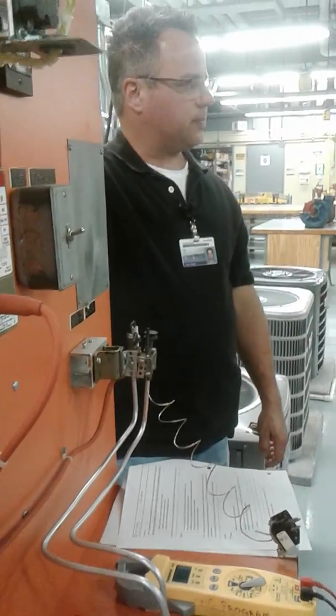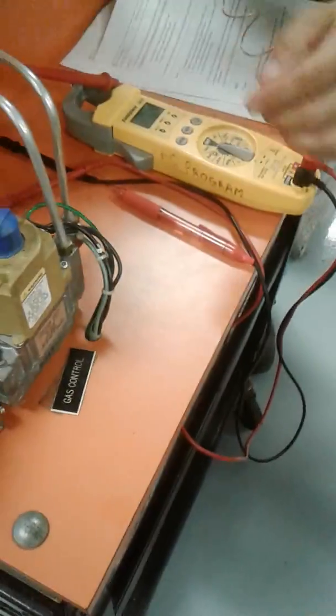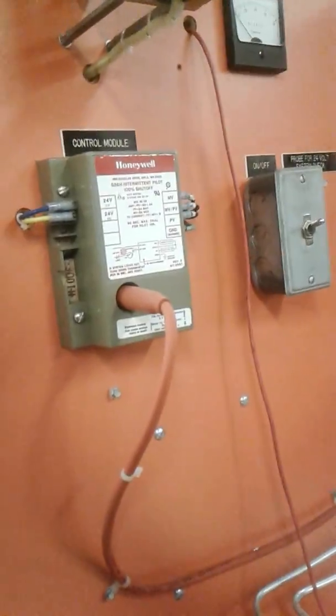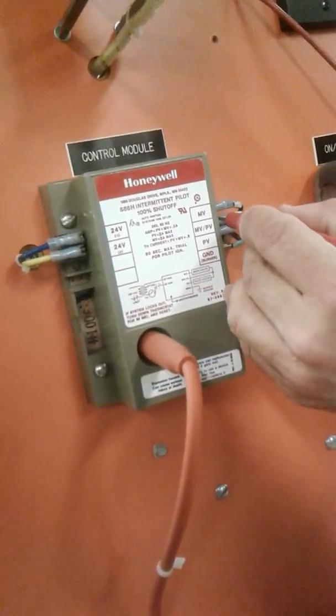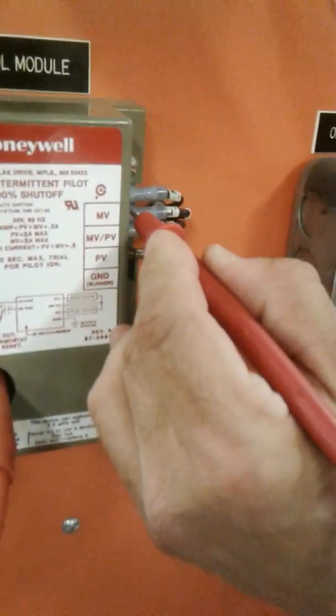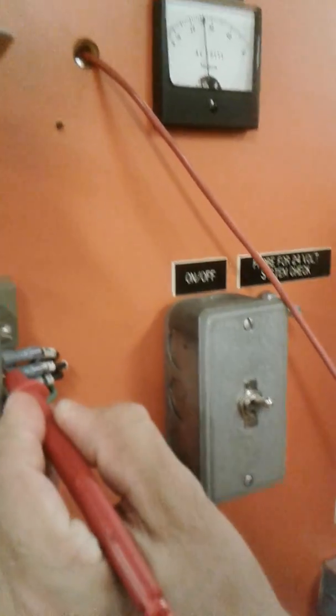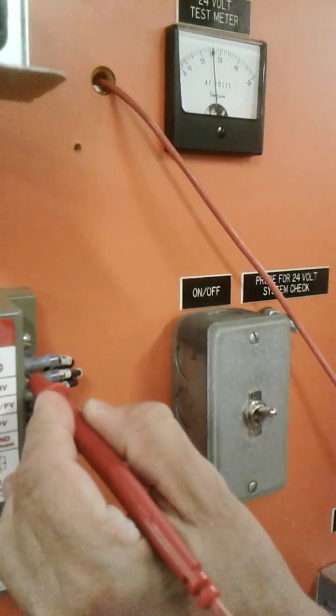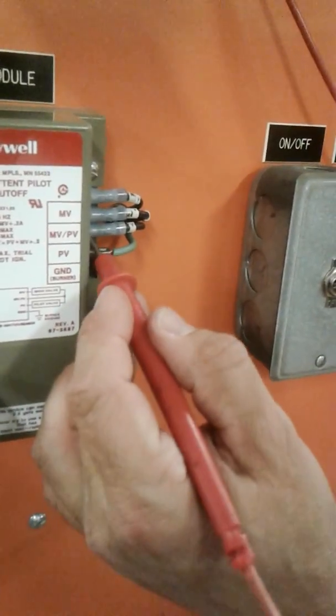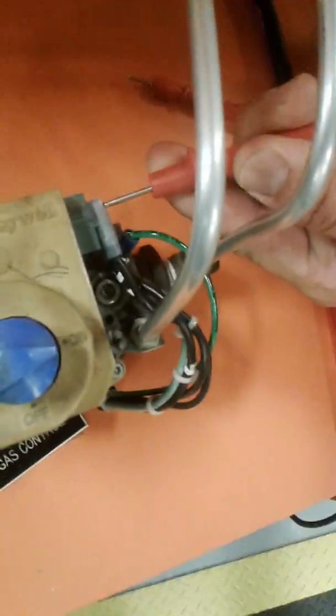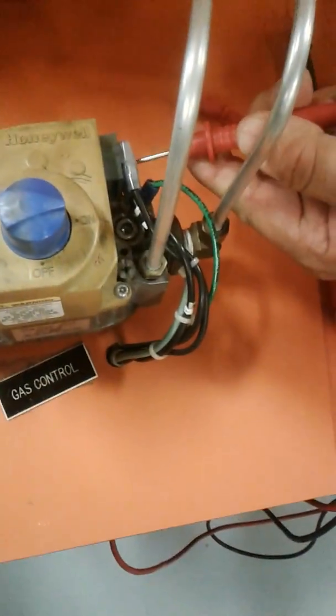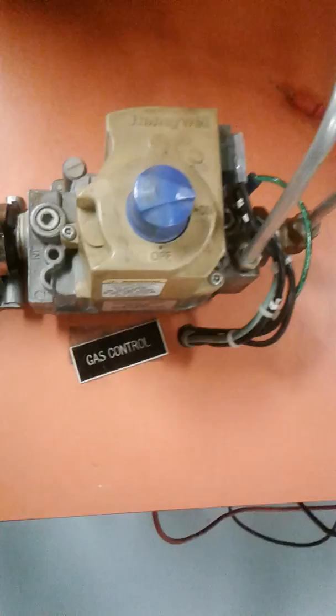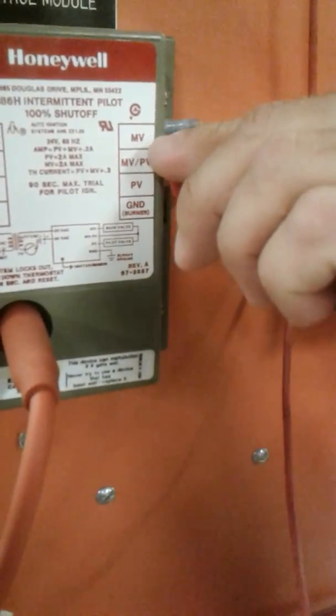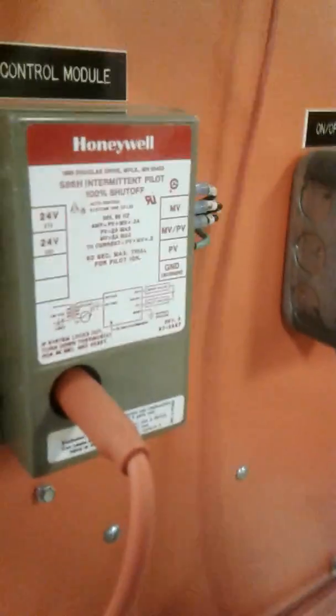Any questions? That's technically a meter. So let's take a look. It should read 24 volts. And it does. 25 volts actually. We're supplying 25 volts to our main valve, and we are, because we know it's open, it's on. And the pilot, because we see the pilot is on. Same thing down here. 25 volts. Okay. Common should read nothing. That's the neutral, or the common, I should say. This is common to here, and this is also common to the pilot valve. It tells you right there.